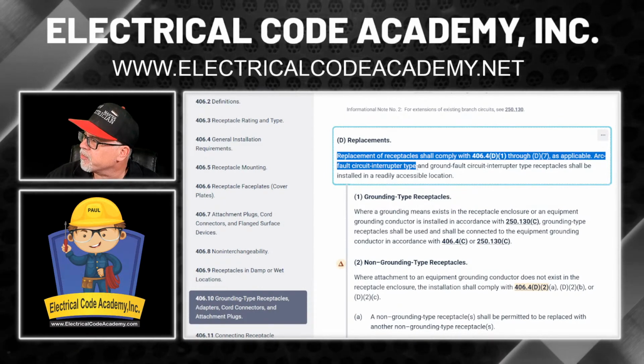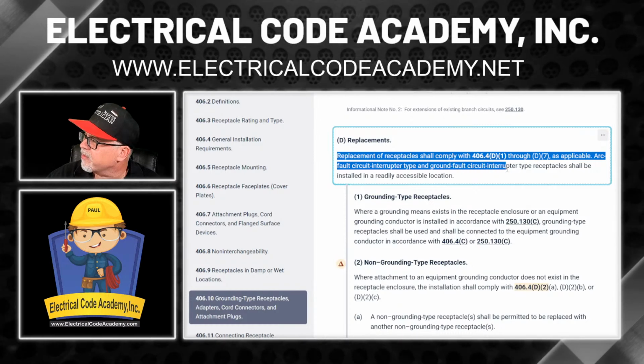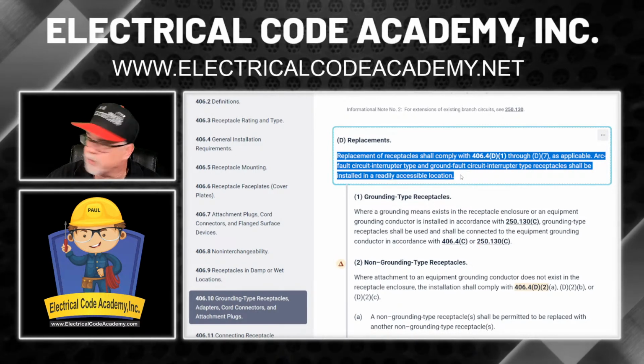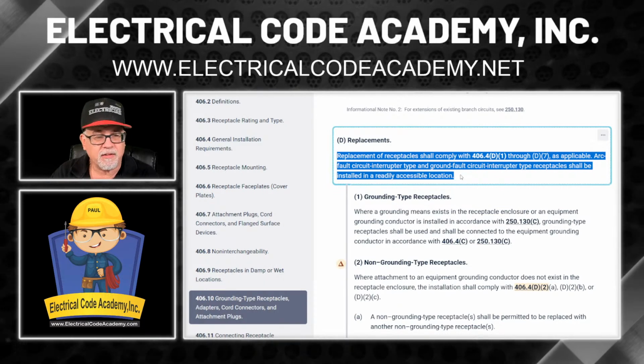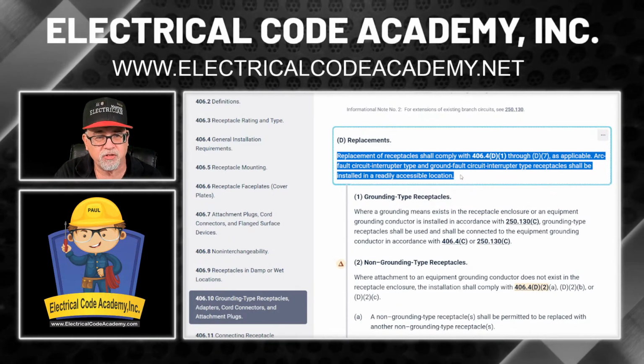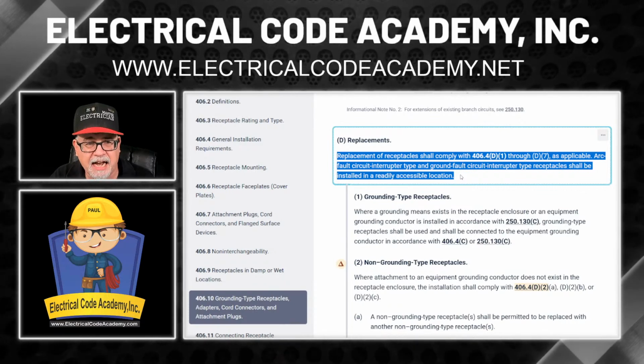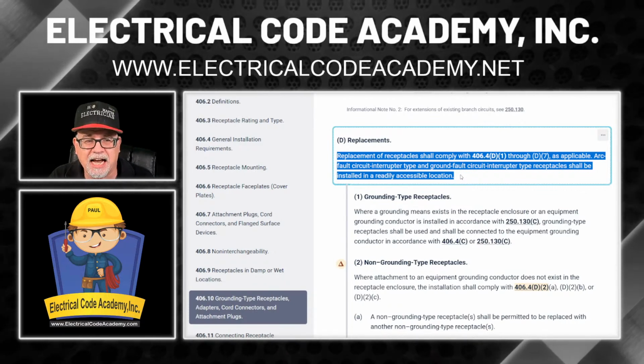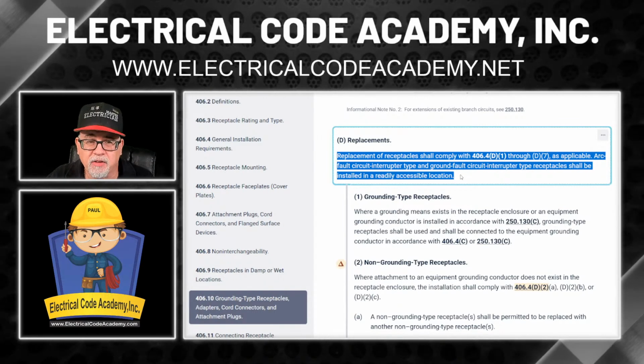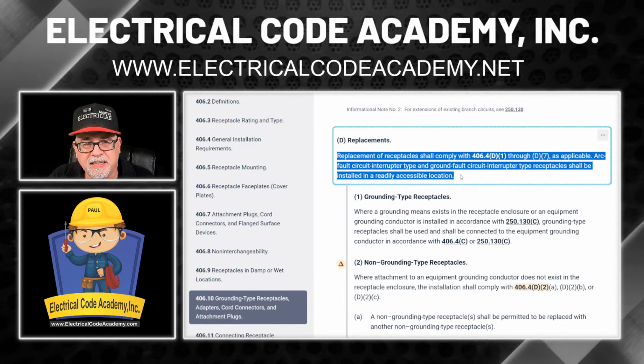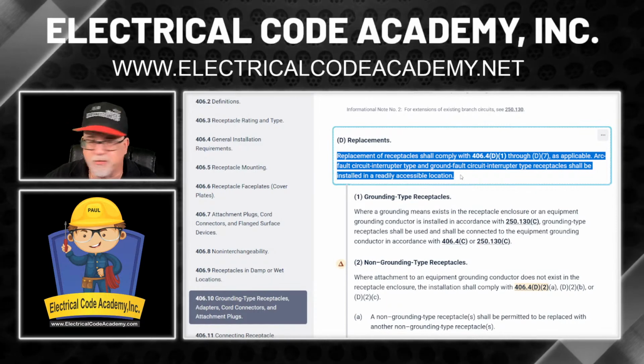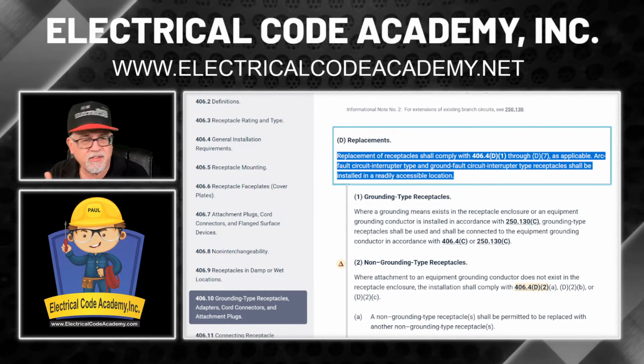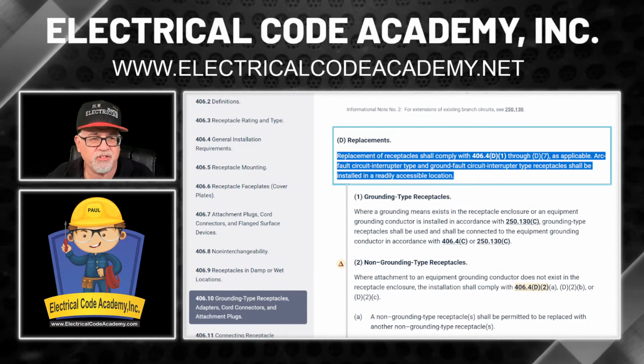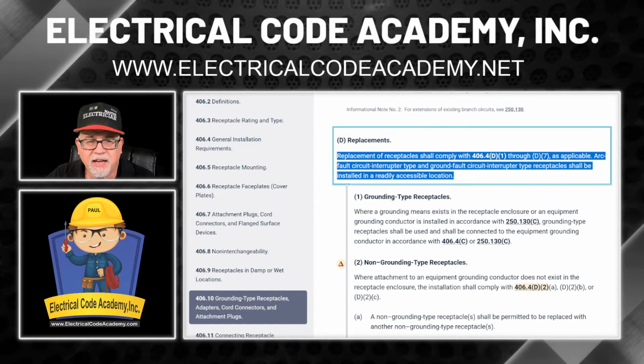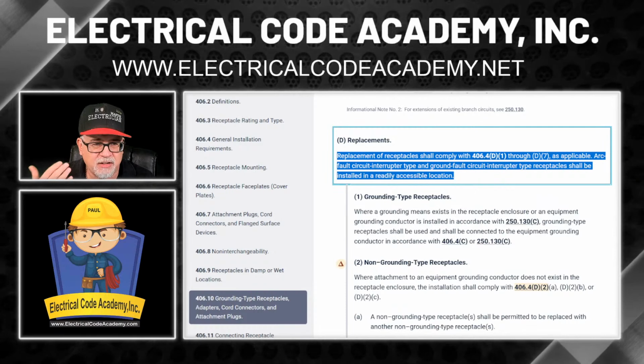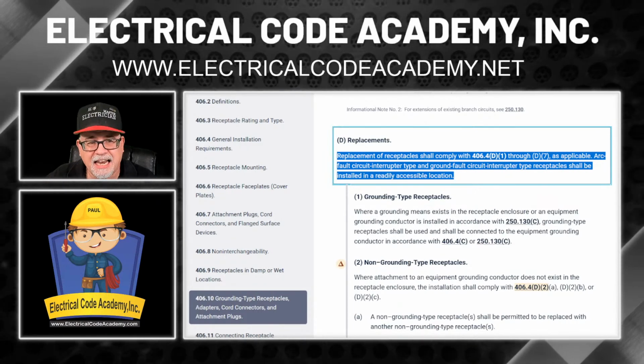Arc fault circuit interrupter type and ground fault circuit interrupter type receptacles shall be installed in a readily accessible location. So one of the options is if he was replacing this receptacle in a location that back then did not require AFCI or did not require GFCI, if the location now requires it, then you're going to have to do something different. It's just not as easy as a swap, okay? Now, we'll do that in a different video. Let's just say that this is a location where he can simply swap out that 2-prong and put in his GFCI like he wants to do.